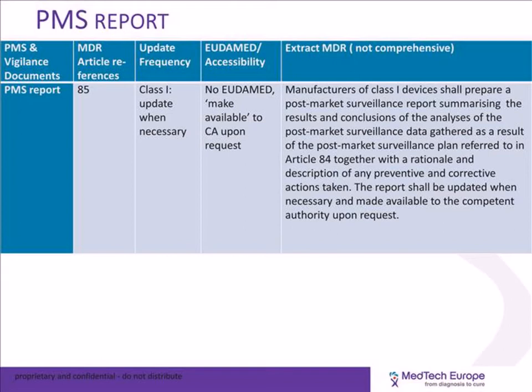What we can anticipate is that we will have a significant increase in the number of local audits carried out by the authority under the medical device regulation. And this local audit can be random or a review of specific classes of devices, or they can be for cause, if the authority are alerted by a certain number of vigilance reports which seem to indicate that there may be an issue with a specific product or class of device.